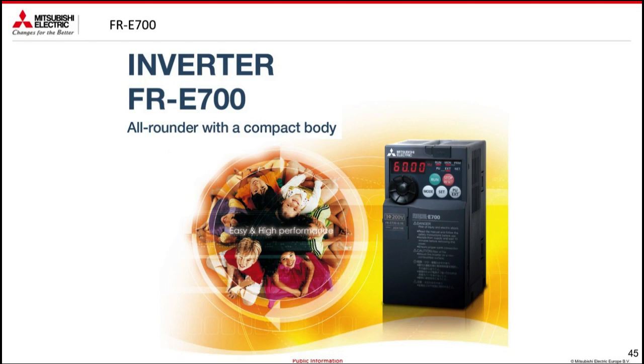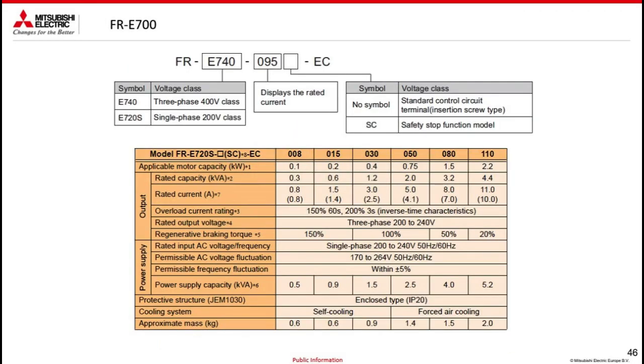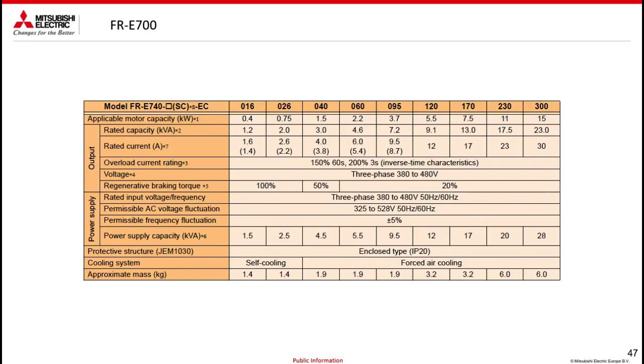Speaking now of the FR-E700 inverter, it has some more functions than the FR-D700. As far as reading the model is concerned, it is exactly the same concept seen previously. As regards the sizes, the FR-E700 also exists in the single-phase version up to a maximum of 2.2 kilowatt, but the nominal current has been increased compared to the previous model, and the size has been increased to 400 volt three-phase. In fact, before it stopped at 7.5 kilowatt, while now we reach 15 kilowatt.